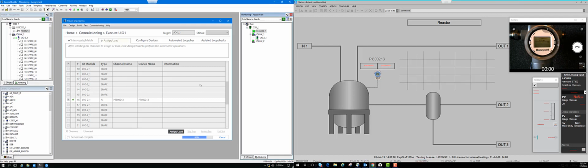And then there's a couple of ways. So there's a couple of things I want to show you in this video, but for the most part, it's going to be Asset Management, which is Field Device Manager with Experion's latest and greatest auto device commissioning functionality. So let's see here. I do have a trend here to my right, so we can view the test. And here to the left, I have the instrument that we're witnessing here on the camera. And I have developed two screens here to cycle at 3 seconds each. So every step, from 0 to 25 to 50 to 75 to 100%, each one of those transition steps is 10 seconds. Okay, so we'll be able to see that 10-second step change. Everything should match on the trend, everything should match on the face of the instrument, and then also on the dashboards.